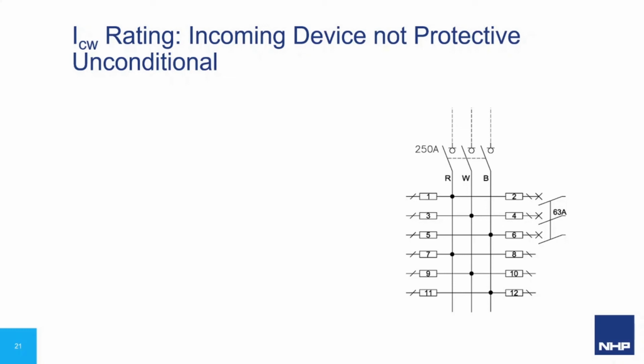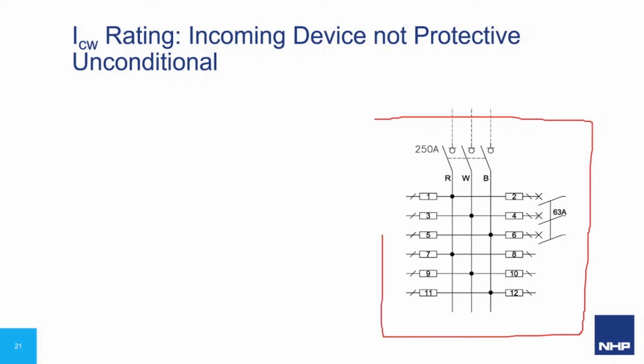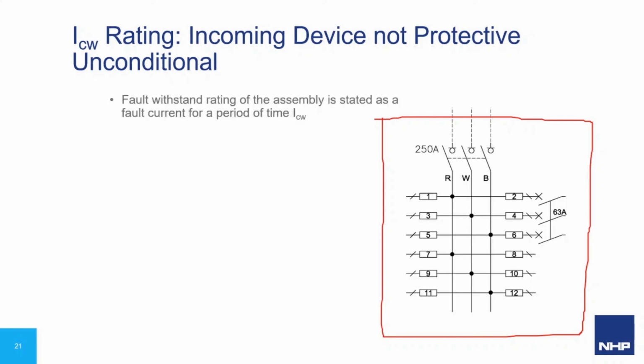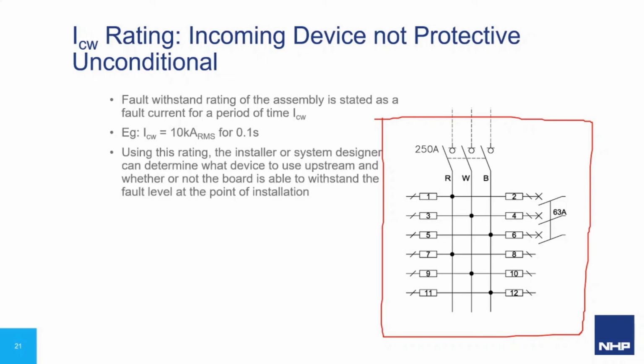The ICW rating is for when our incoming device is not protective. Again, for clarity, I'll draw a box around everything that's inside our assembly. The fault withstand rating of the assembly is stated as fault current for a period of time. For example, 10 kA for 0.1 seconds. Using this rating, the installer or system designer can determine what device to use upstream and whether or not the board is able to withstand the fault level at the point of the installation where it will be installed.